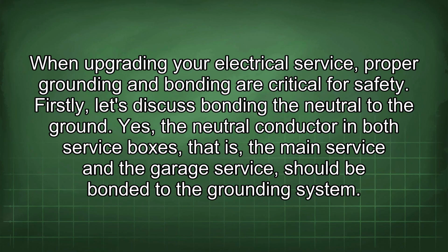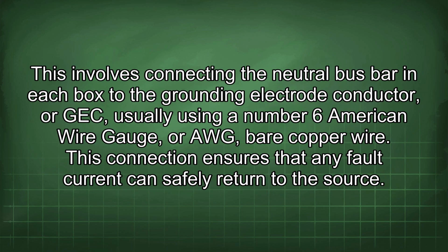When upgrading your electrical service, proper grounding and bonding are critical for safety. Firstly, let's discuss bonding the neutral to the ground. Yes, the neutral conductor in both service boxes, that is, the main service and the garage service, should be bonded to the grounding system. This involves connecting the neutral bus bar in each box to the grounding electrode conductor, or GEC, usually using a number 6 American wire gauge, or AWG, bare copper wire. This connection ensures that any fault current can safely return to the source.